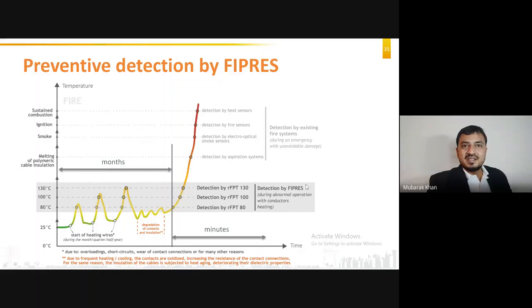This graph we have already seen, right? This remote fire prevention thermolabels or visual fire prevention thermolabels detect the overheating of the joints in this zone, in the range of 80 to 130 degrees Celsius. That is why if you detect it in this zone, you will be able to avoid any hazards occurring, you'll be able to avoid any fire scenario. This will make your system safer. So this is the achievement we get by remote monitoring at a particular temperature.